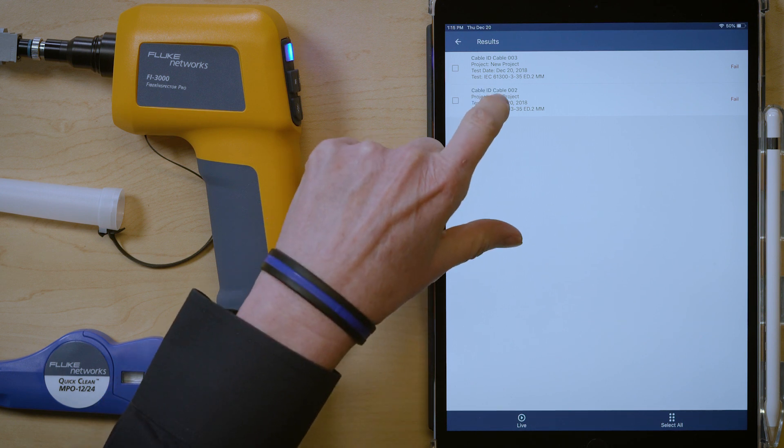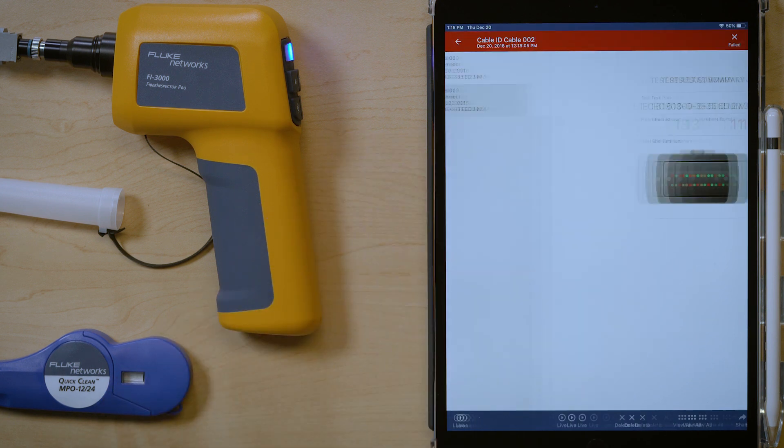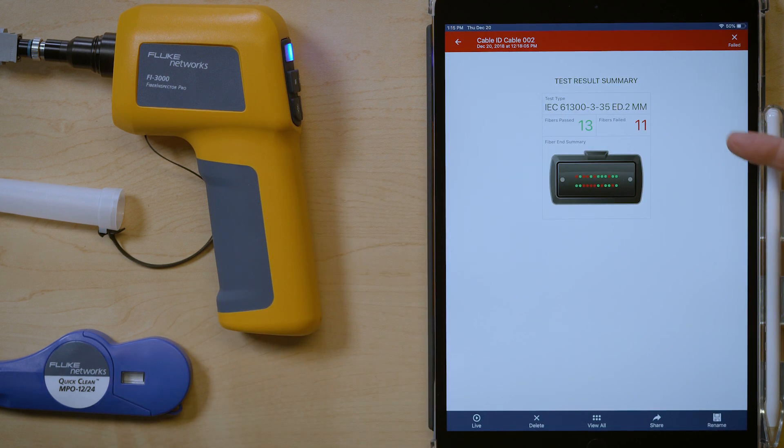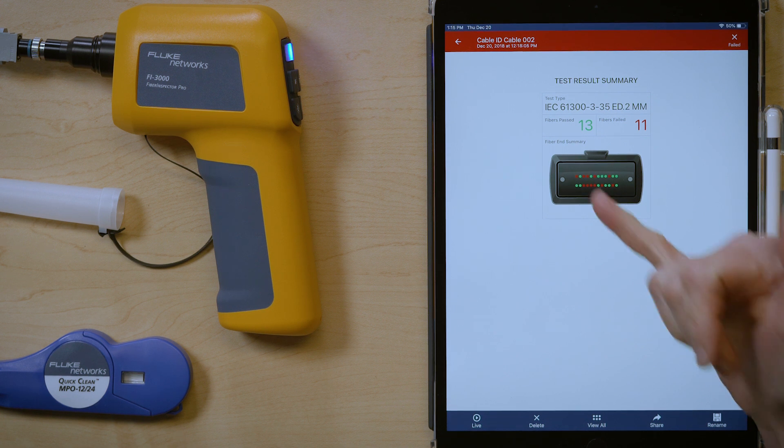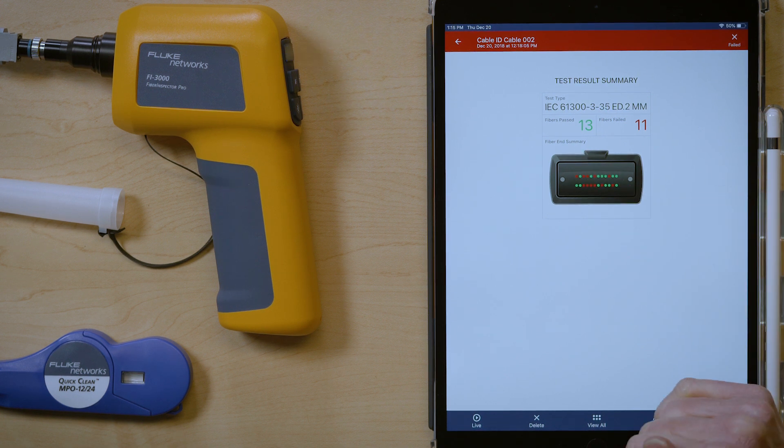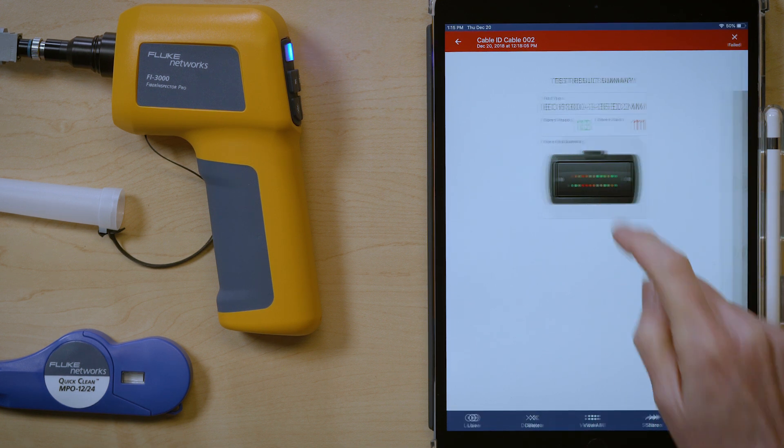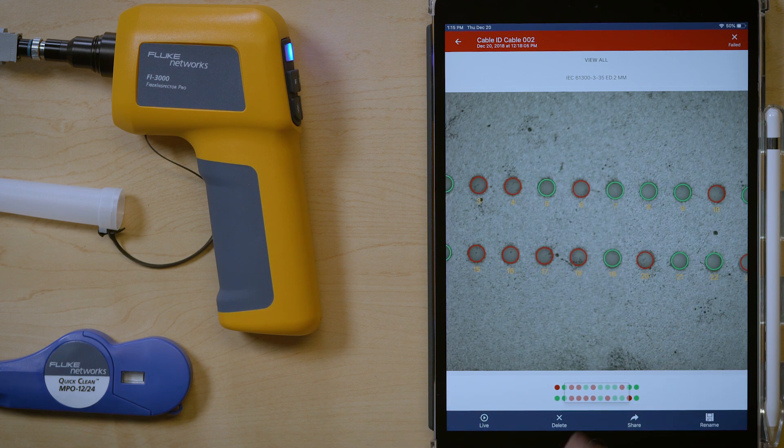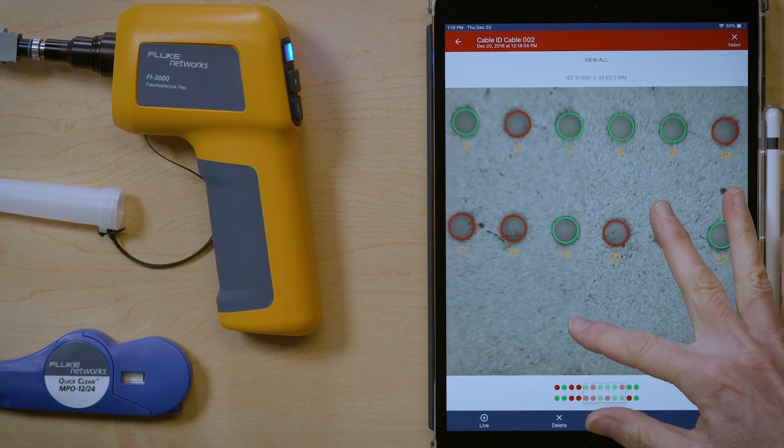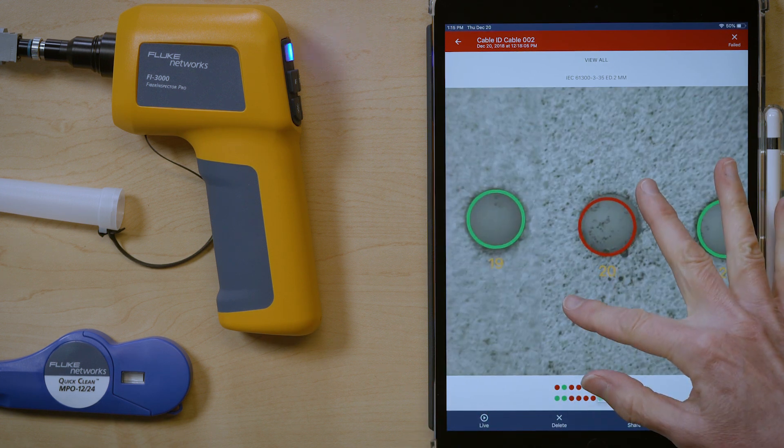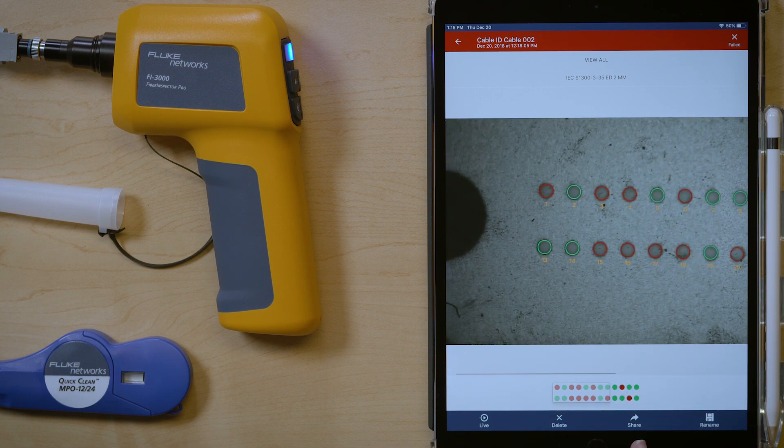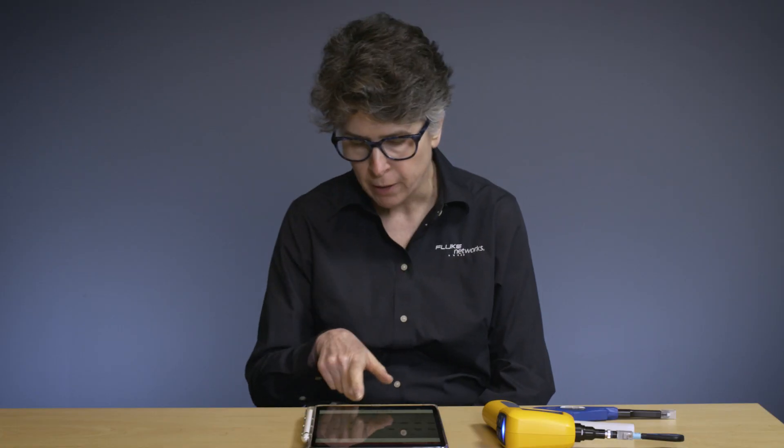Right now I have two results saved. Let's go ahead and look at cable 2. And you can see this was a 24 fiber test result where 13 passed and 11 failed. I can go in, look at this just like I have done before. We showed on earlier videos. But I also can share it.